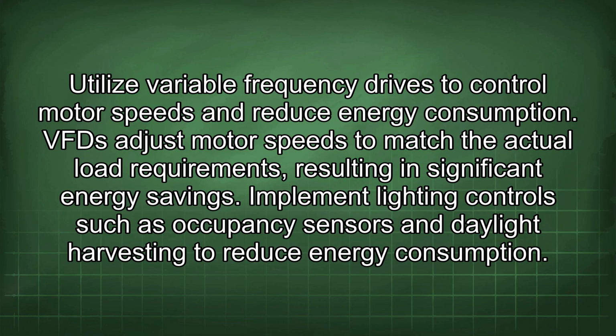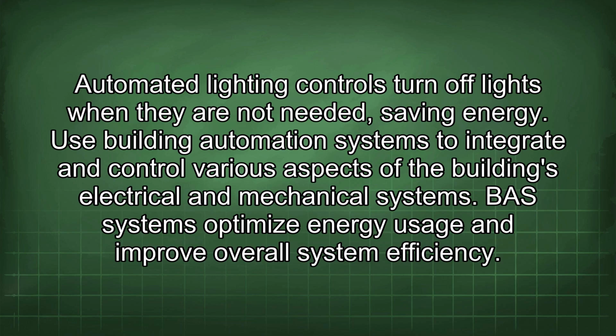VFD adjusts motor speeds to match the actual load requirements, resulting in significant energy savings. Implement lighting controls such as occupancy sensors and daylight harvesting to reduce energy consumption. Automated lighting controls turn off lights when they are not needed, saving energy. Use building automation systems to integrate and control various aspects of the building's electrical and mechanical systems. BAS systems optimize energy usage and improve overall system efficiency.